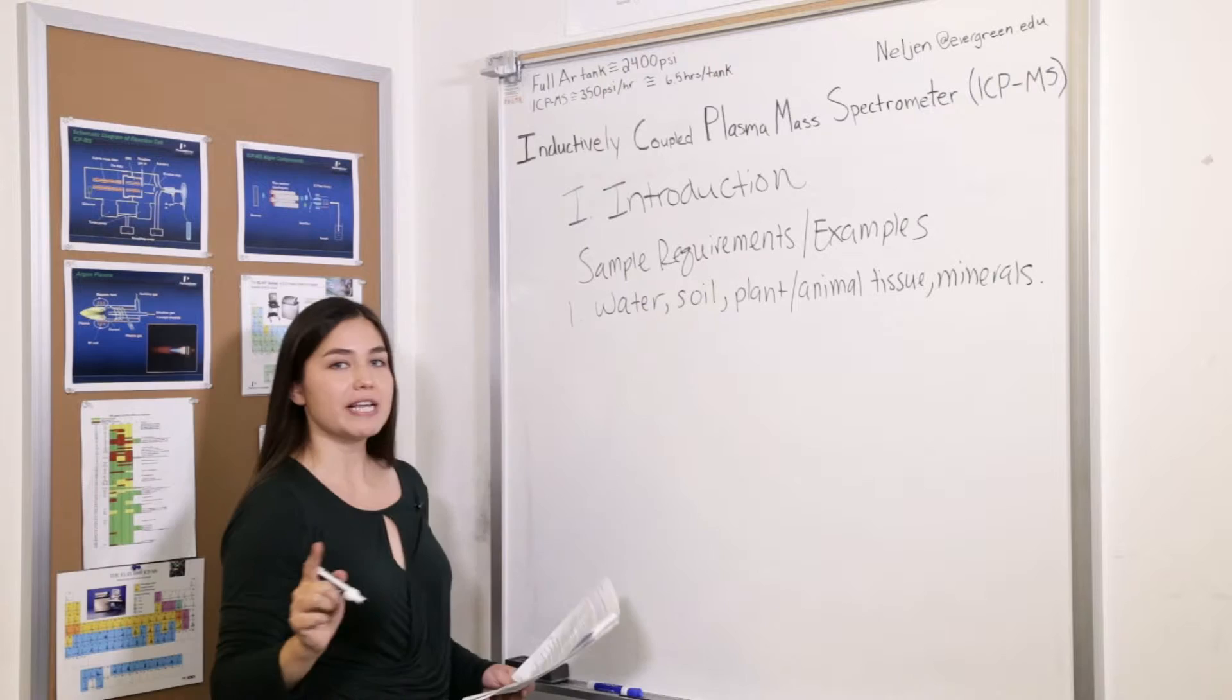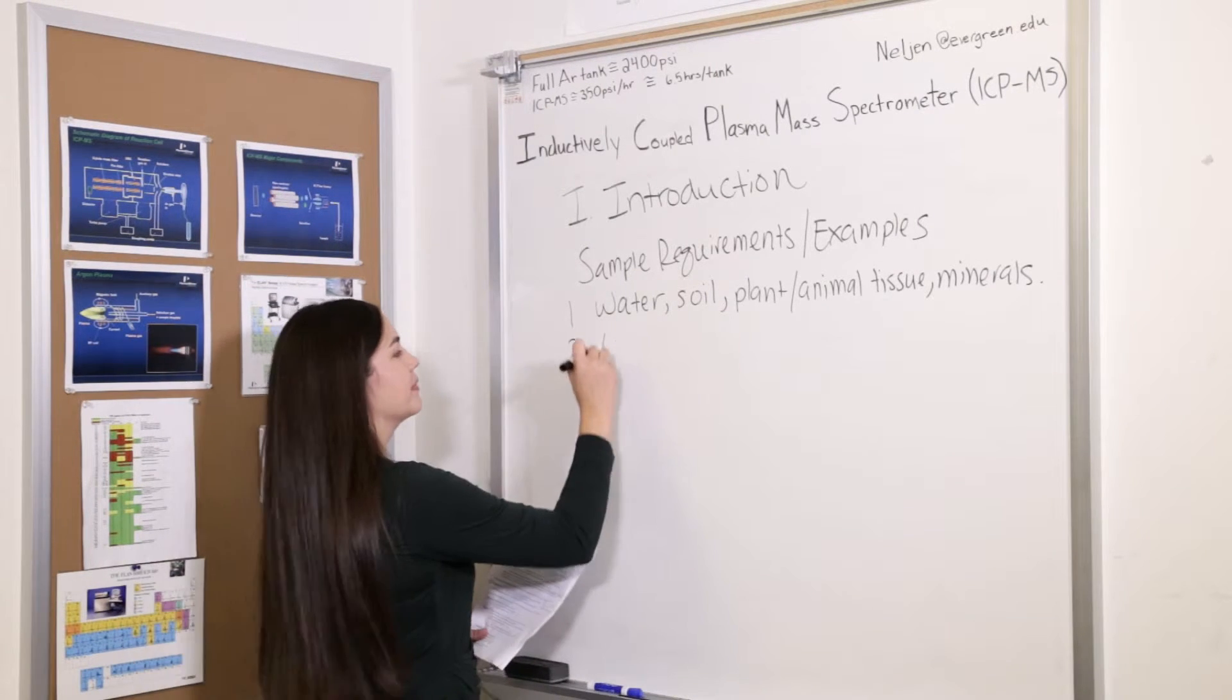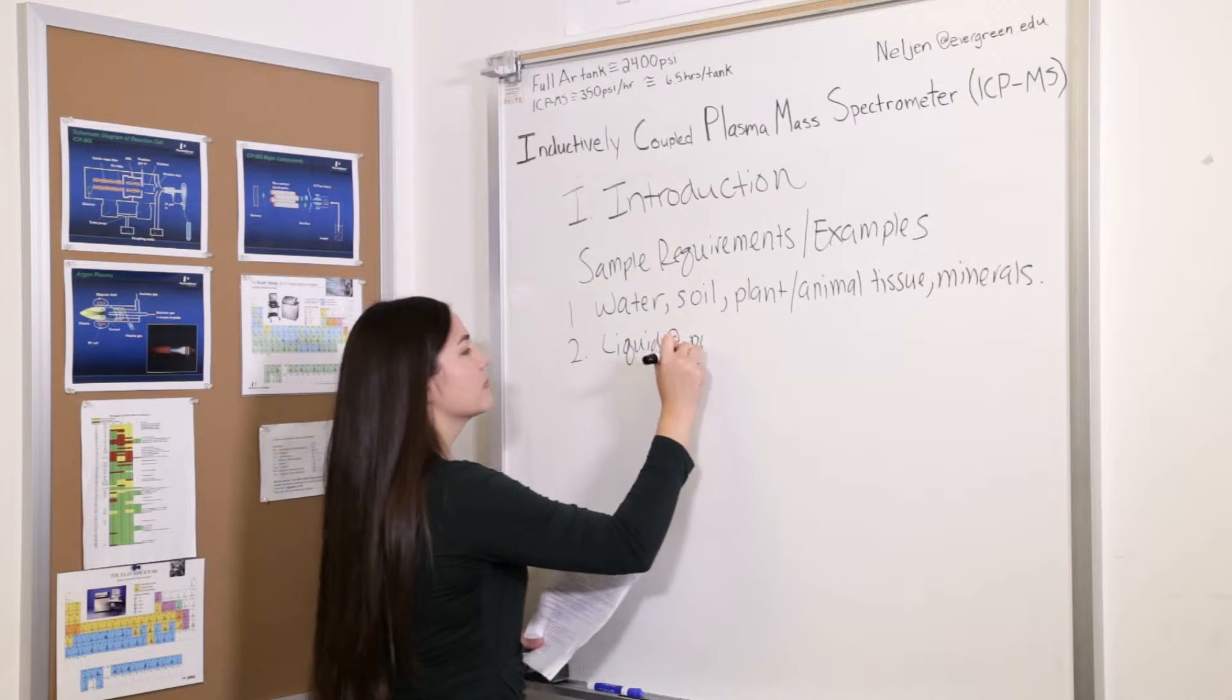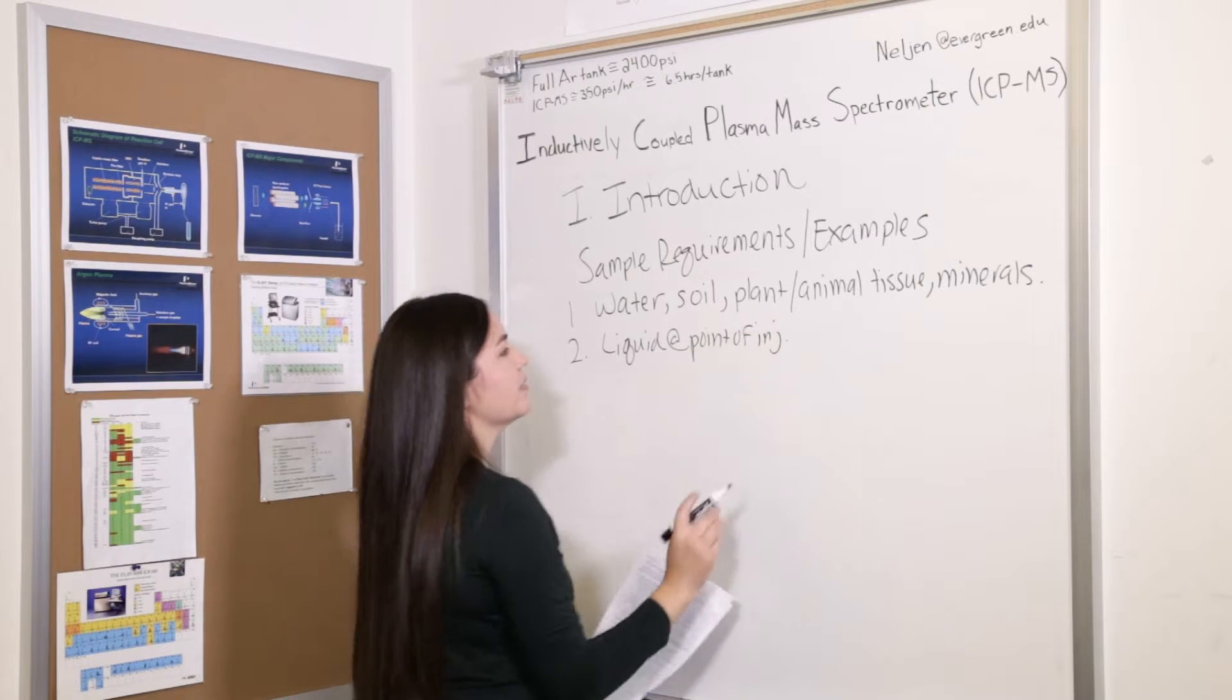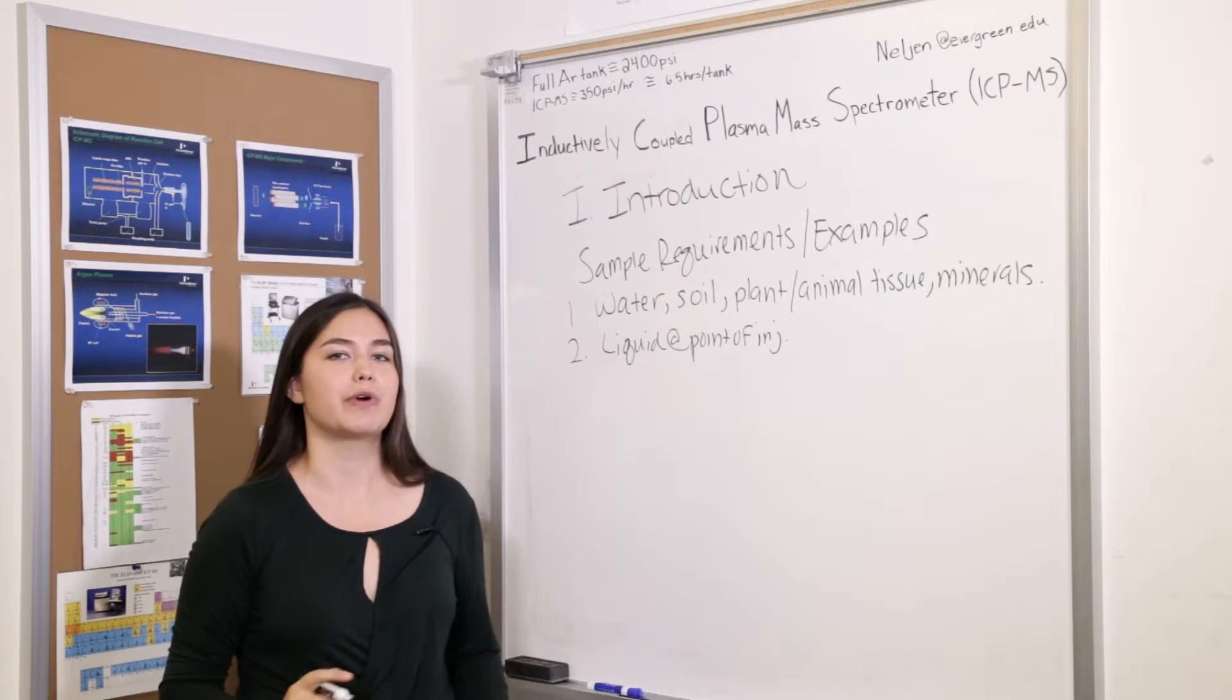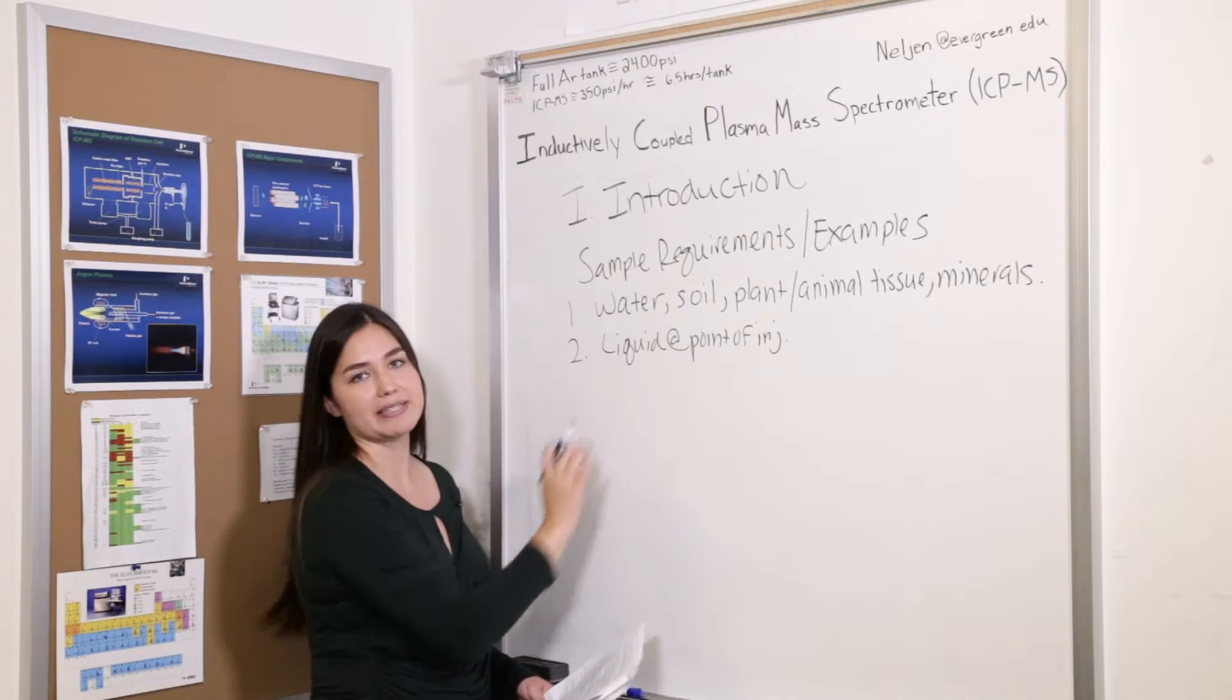Our first sample requirement is that our sample must be liquid at point of injection. So if we are running any of these solid sample types, we would want to make sure that we're first performing a digestion and an extraction before we can run it on the ICP-MS.